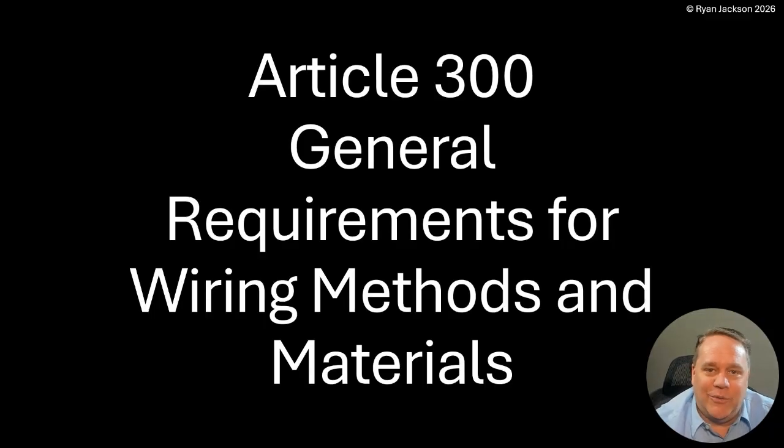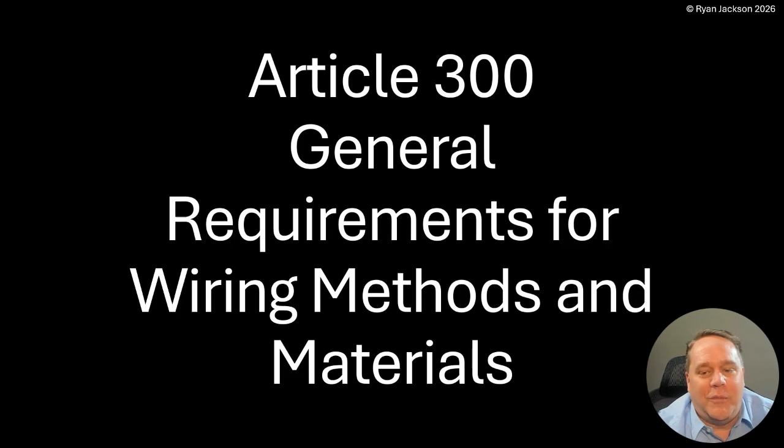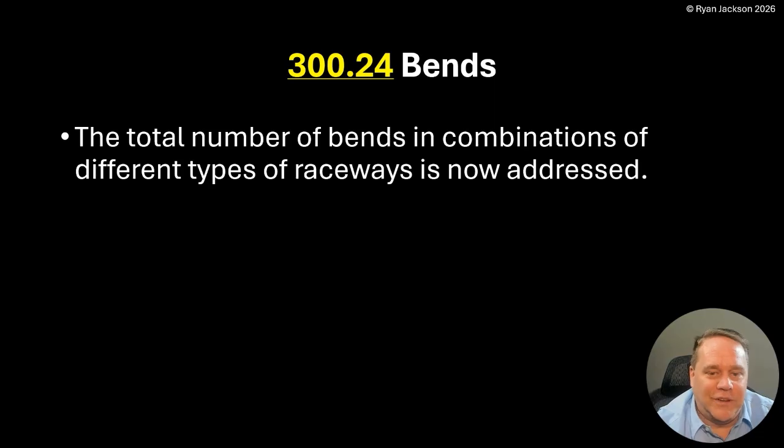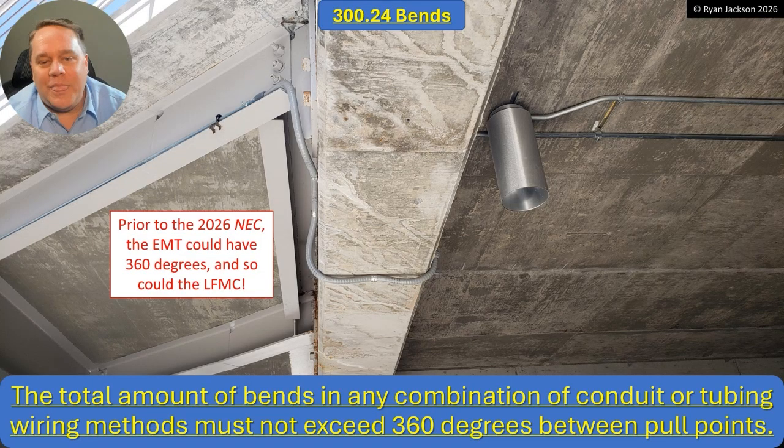Well, it depends on which edition of the code. Prior to the 2026, the answer was yes — you could absolutely do that. My buddy Russ up in Boston caught this and brought it to the attention of the code making panel, and everybody was shocked that he was dead right: it was not a violation. So Article 300 — general requirements for wiring methods and materials — 300.24, Bends: the total number of bends in combinations of different types of raceways is now addressed.